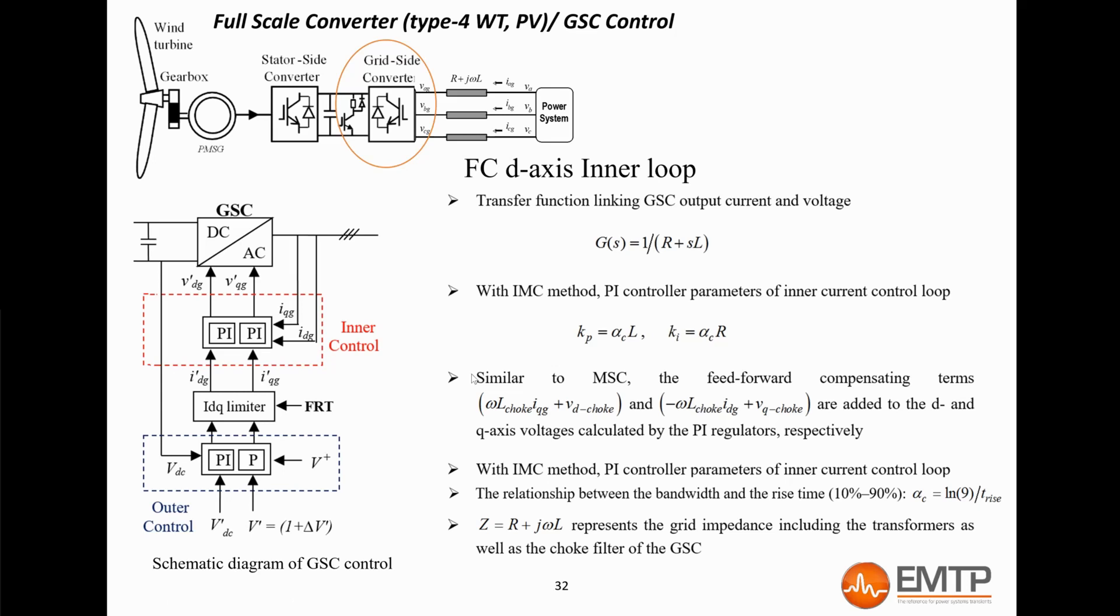To summarize, the outer loop maintains the DC voltage of the DC bus. For example, if the wind increases, the machine-side converter will inject more current into the DC bus in order to get more real power from the wind. This additional injection will tend to increase the DC bus voltage. However, the d-axis control loop of the grid-side converter will maintain the DC voltage to its nominal value by increasing the grid d-axis current, which corresponds to the real power. In the end, the additional power from the wind increase goes through the two converters straight to the grid.